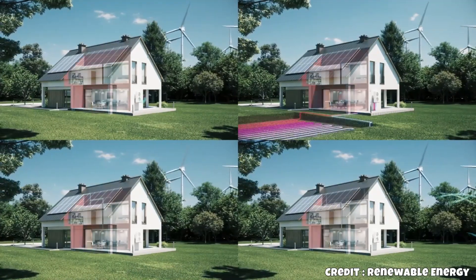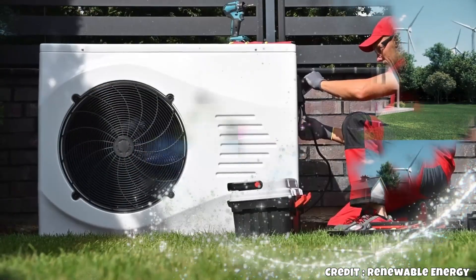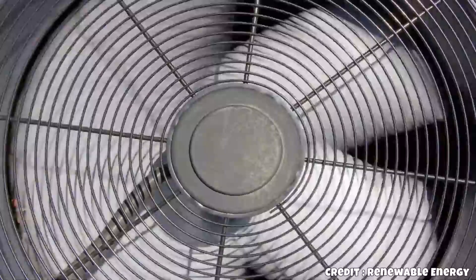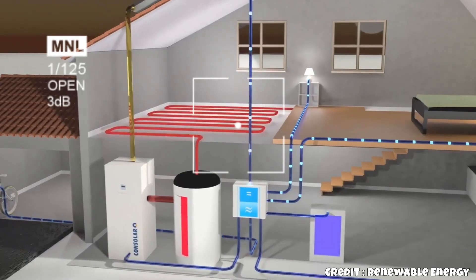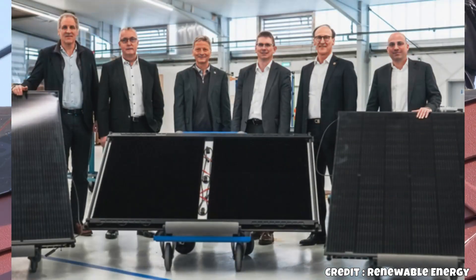The Consolar collector effectively replaces the bulky and noisy outdoor unit of a heat pump. Instead, PVT collectors are installed on the roof and connected to an indoor unit, serving as a superior and more powerful heat source. Heat pumps operate by extracting heat from the environment — groundwater, soil, or outside air — and their efficiency increases with higher ambient temperatures, as less energy is required to heat the building.